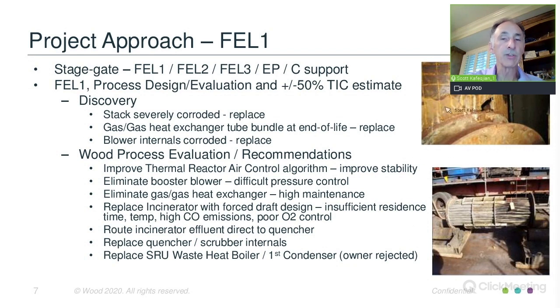shows a portion of the stack. It's basically corroded through, and was not in a condition where it could be repaired. The gas-to-gas heat exchanger also showed some severe distortion of the tubes and needed a tube bundle replacement. And the booster blower internals were also found to be badly corroded due to carryover of liquid from the scrubber.